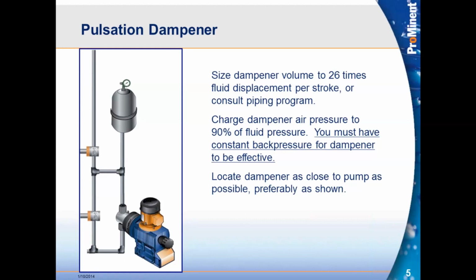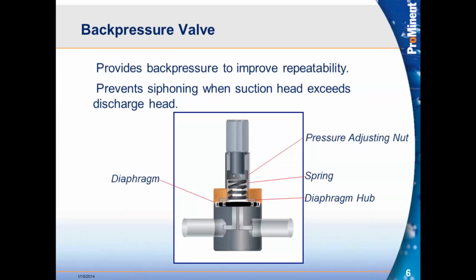So it's a good slide to show where it's installed. So regulating the back pressure, this is kind of a cutaway view of the back pressure valve, what you might see. One of those is the inlet, we'll call it to the left. Now that would be oriented a little bit closer to the center. So it's going to come in the center, and then the one on the right being the exit is going to be towards the outer edge of the diaphragm.